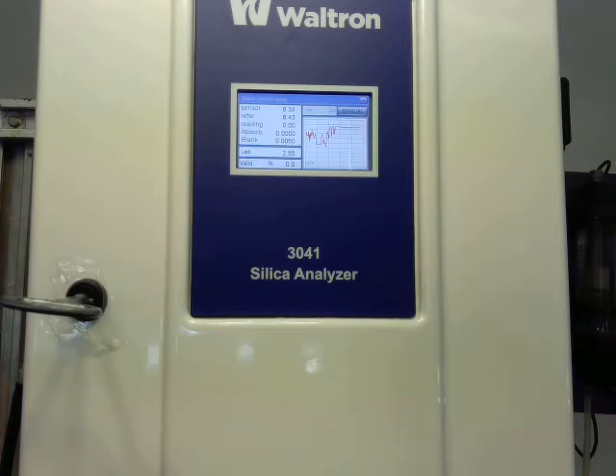So we should be coming up on the end of this mix time right now. Again, the whole sample time is a little different for each analyzer, but it's about a 10-11 minute process of rinsing, mixing, and you get your result near the end of that 10 minutes. And then there's a little bit of wait time added to each cycle. So you're looking at about 20 minutes in between readings, and again, that gives you about a month's life of reagent usage.